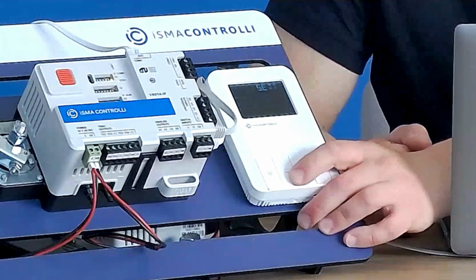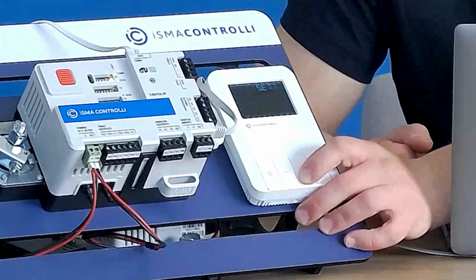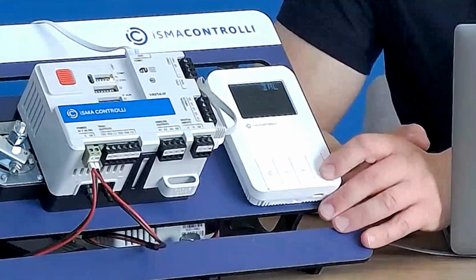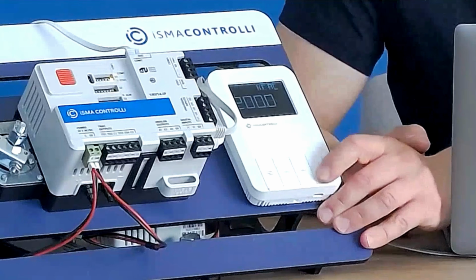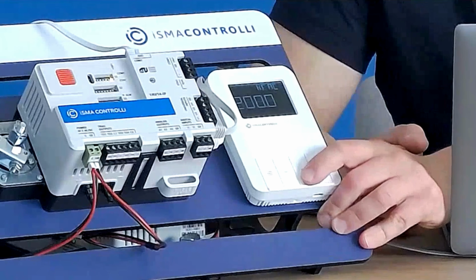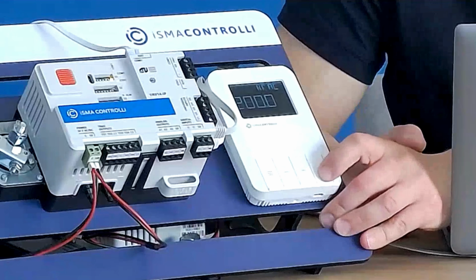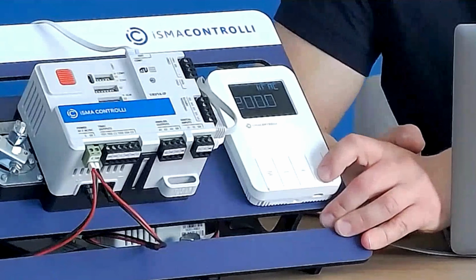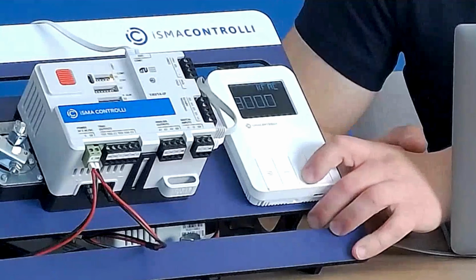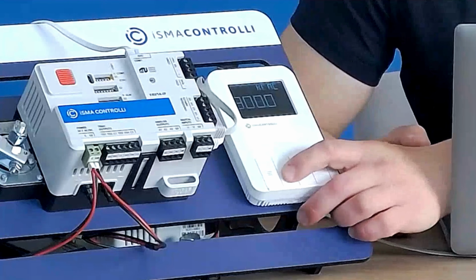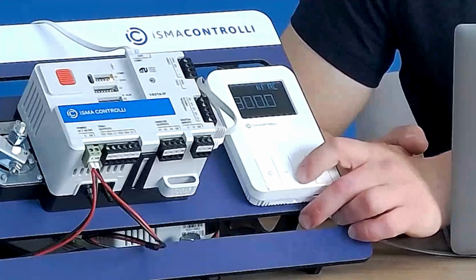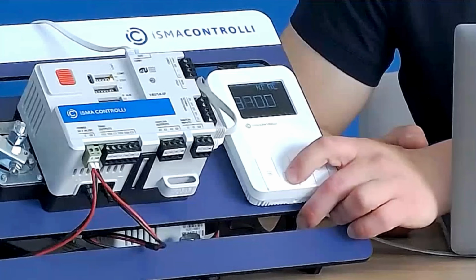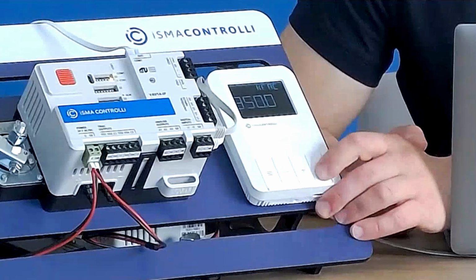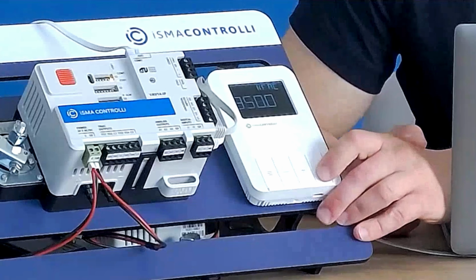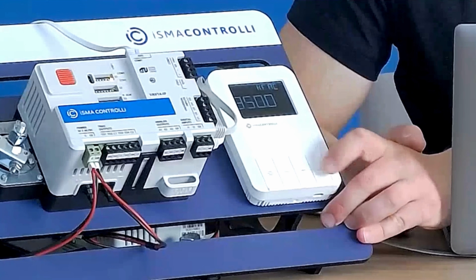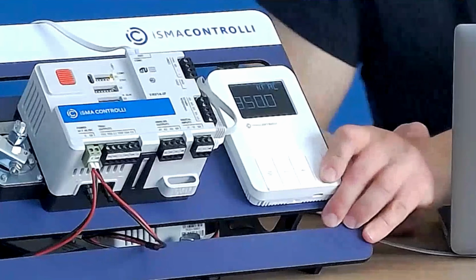So in configuration and application configuration, the settings are the flow settings and a balancing option. When I enter the balancing option, I will go into the balancing possibility, and I will start with setting the K-factor. I can set the K-factor using the buttons available. So I will set it to 350. Sorry, 350.